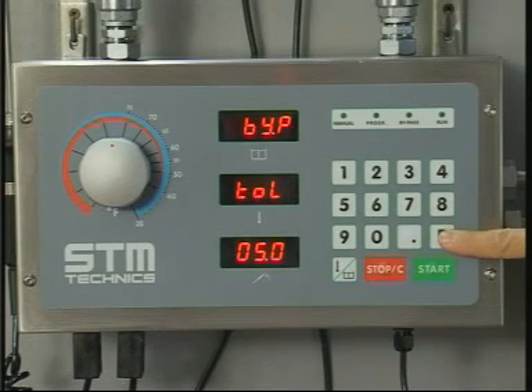BYP-TOL. This display appears if in the previous option the temperature control for the bypass has been chosen. The tolerance of the intervention of the bypass is given in degrees. The set degrees will be referred to the unit of measure selected before. If instead of temperature, time control is chosen, the display will be BYP SEC and the length of time is shown in seconds.